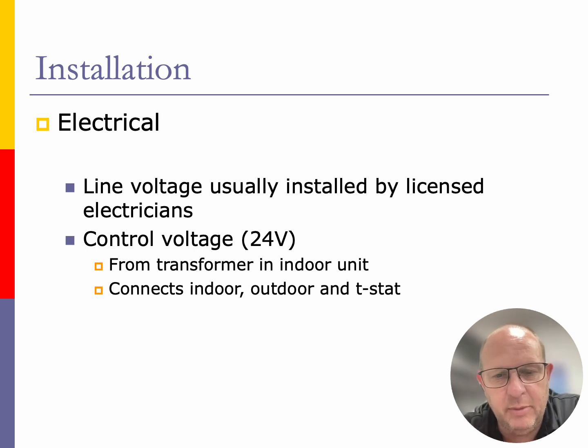All the wires should run into the indoor unit and be distributed out. We're talking about our thermostat wire or a control wire needing to be brought into the indoor unit and then distributed out to different components that we want to run. Those components are the thermostat and the outdoor unit. So whether it's an air handler or a furnace, all of our connections are going to be made in the indoor unit itself.